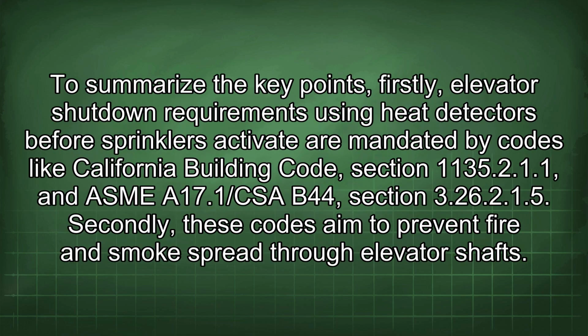To summarize the key points, firstly, elevator shutdown requirements using heat detectors before sprinklers activate are mandated by codes like California Building Code, Section 1135.2.1.1, and ASME A17.1/CSA B44, Section 3.26.2.1.5. Secondly, these codes aim to prevent fire and smoke spread through elevator shafts.